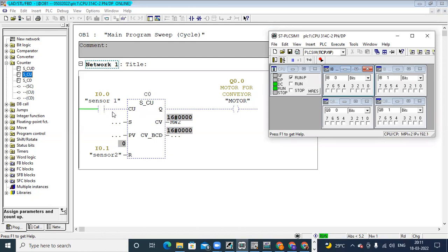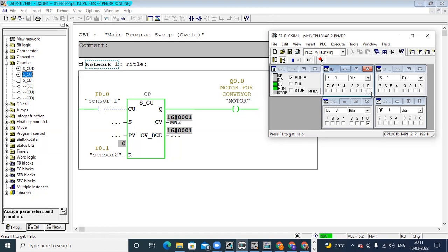Now in CV the value is zero and the output status is off. When I give input I0.0 on, you can see in CV the value becomes 1 and output Q is on. Next I remove the input — input is off — but the output status is still on, and in MW2 the value is 1. When I give the input again, it becomes 2. The number of times I make the input on and off, it is counting up — it is incrementing.